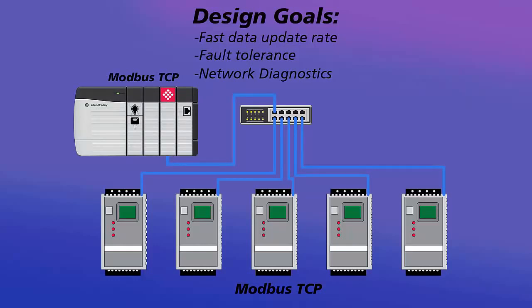A single client has no problem communicating with several different servers on the same network, but there are some considerations using such an arrangement. The client will open communications with each drive one by one, sending a read or write command, and waiting for a response. Once the client receives the response from the server, it will close the connection and move on to the next drive. The issue is if one drive is taken offline unexpectedly, it will slow down communications with the 4 other drives while the client waits for its requests from the missing drive to time out.